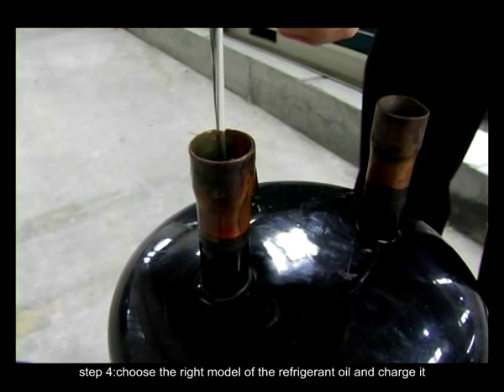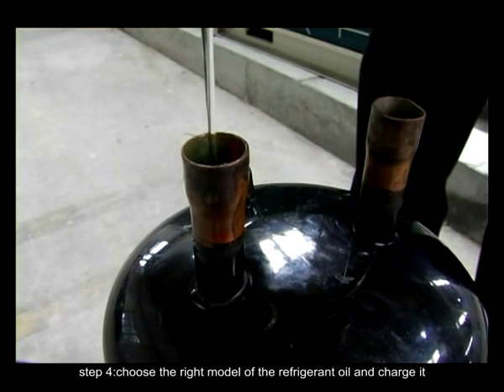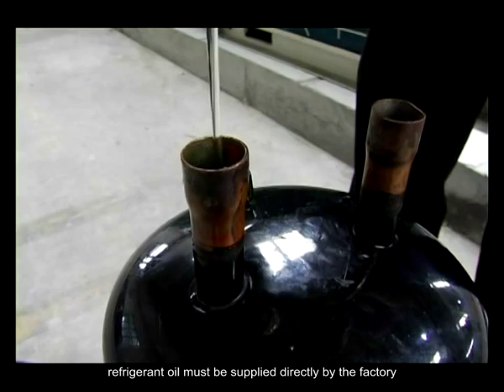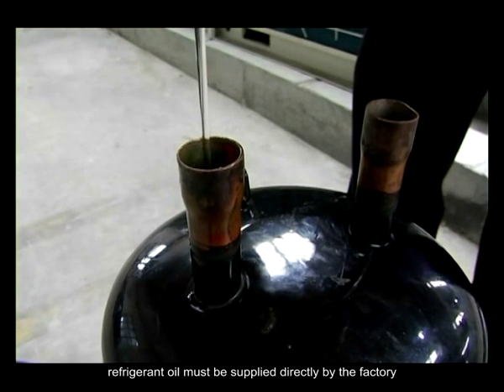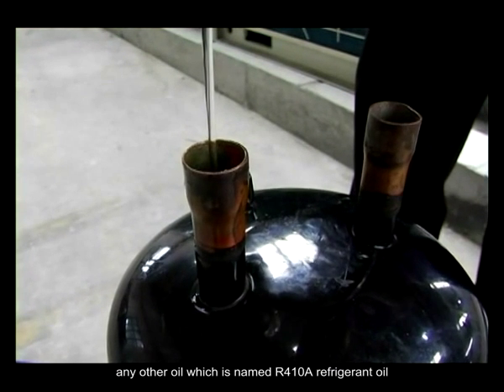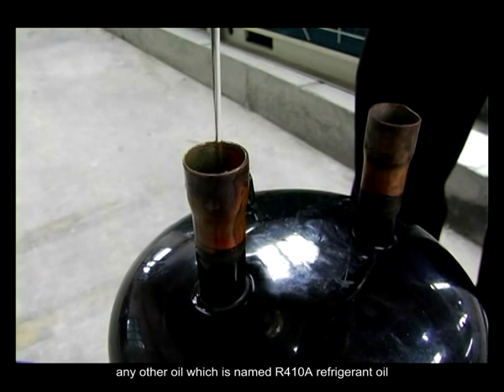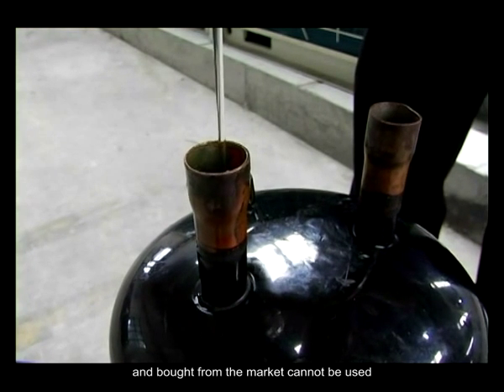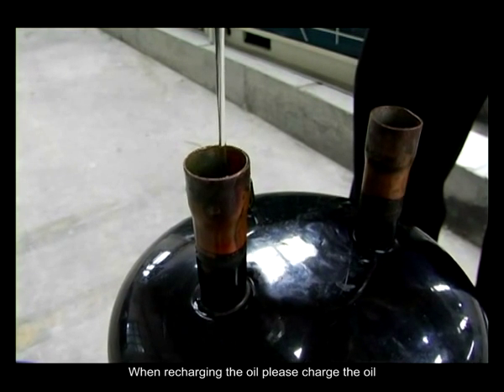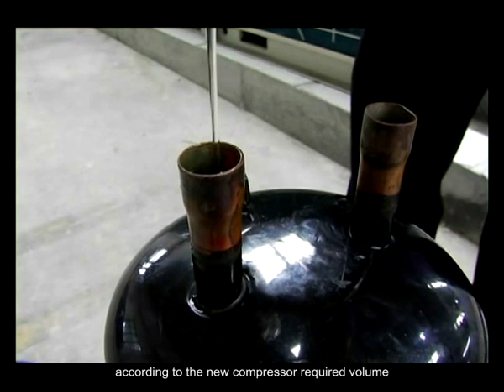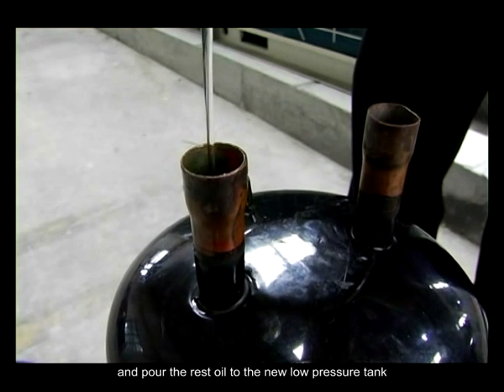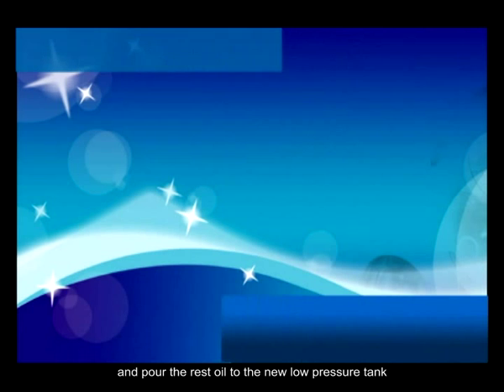Step 4. Choose the right model of refrigerant oil and charge it. Refrigerant oil must be supplied directly by the factory. Any other oil named R410A refrigerant oil and bought from the market cannot be used. When recharging the oil, charge it according to the volume required by the new compressor and pour the rest of the oil into the new low pressure tank.